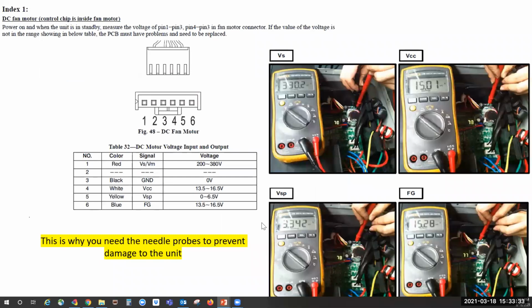Now, when checking, this is again where you need your needle probes. I don't like to, but in a pinch, if you didn't have needle probes, you can use some smaller wire, like thermostat wire, strip it back, and put them in there. Sometimes you don't get as good of a connection as you should. So when you're checking the 5-wire motor, the control chip is in the motor. You want to check between pins 1 and 3, and you should have between 200 and 380 volts DC. Once again, you're going to check your service manual for exact voltages on this. Then you're going to check for control voltage between pin 3 and 4, 5, and 6.